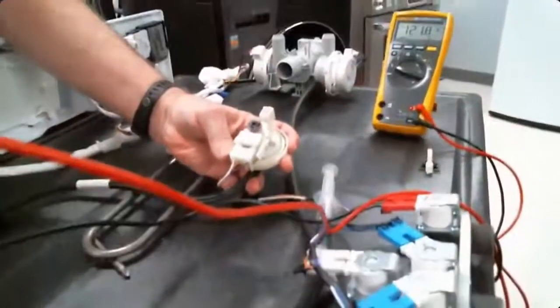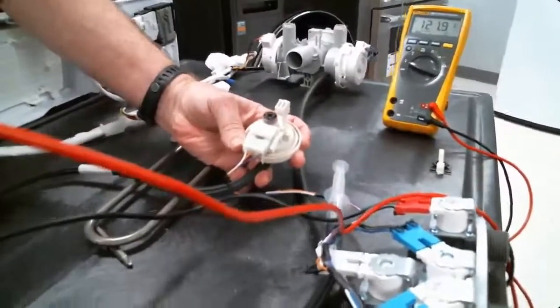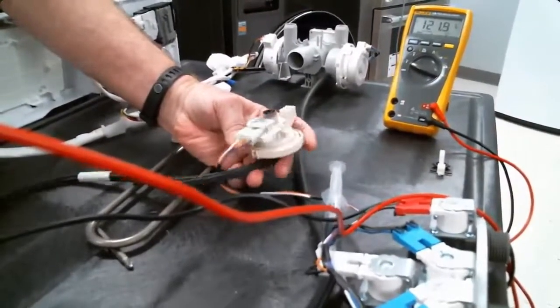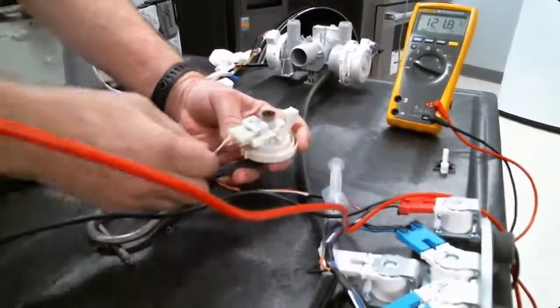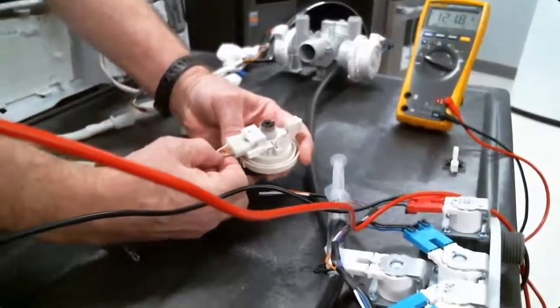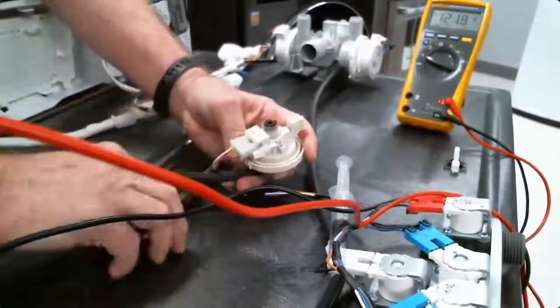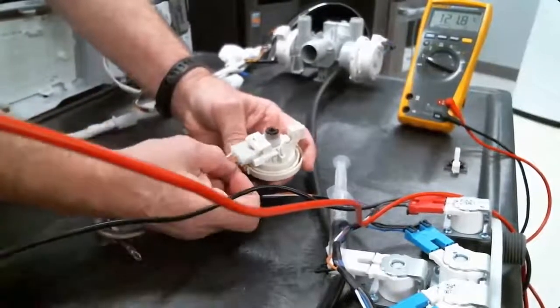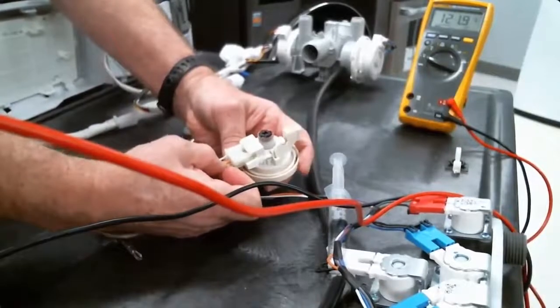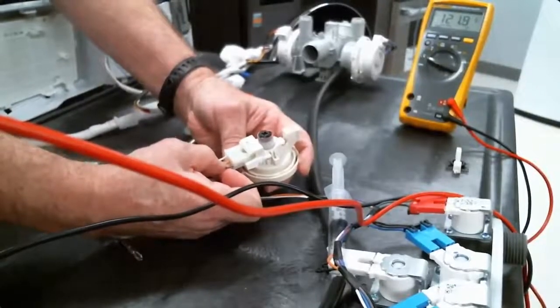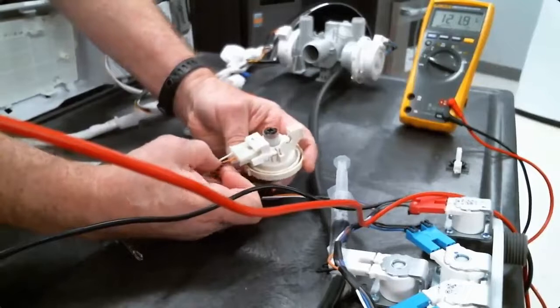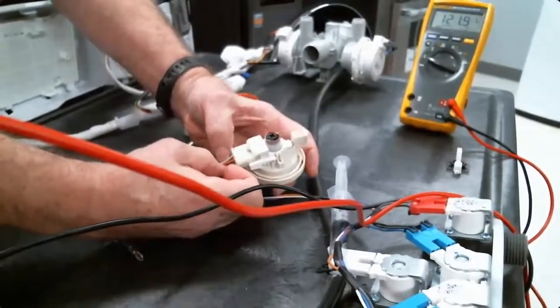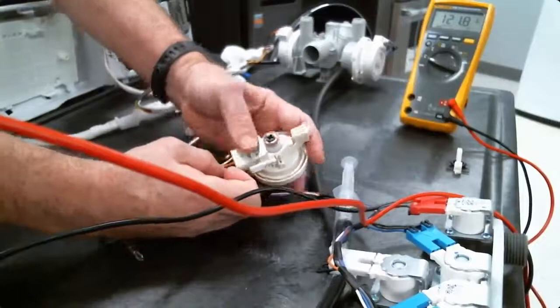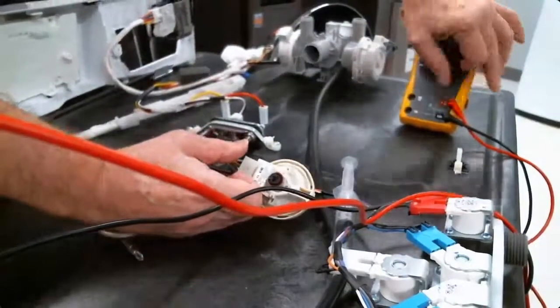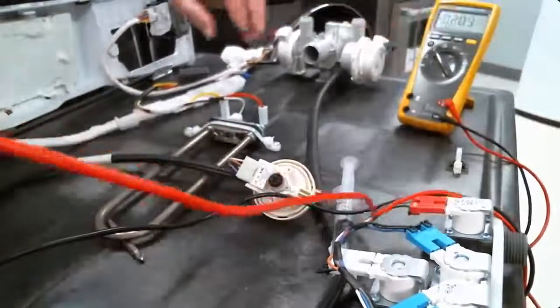This uses frequency to determine what the water level is. You can actually test these. There is a common terminal. In this case, the common terminal is your violet wire. The other two wires are two halves of an oscillator. So basically, when I go from violet to orange with power on, I should get approximately 2.5 to 3 volts DC, and I should get the same thing from white to violet. So let's switch this to DC voltage and quickly check that for you too.